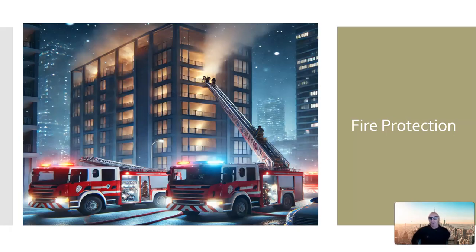These regulations, they designed them to keep people safe, and to help prevent buildings from being too large or too tall for their construction type and fire protection systems. You see this in table 504.3, which actually reflects heights in feet. 504.4 discusses stories or indicates stories, and 506.2 floor area. These provide the maximum limits based on occupancy and construction type.